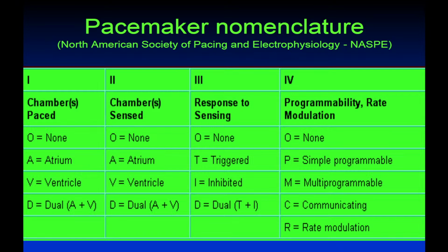We must take into account the pacemaker nomenclature by the North American Society of Pacing and Electrophysiology, NASPE. These devices have a few letters: the first letter means chamber paced, the second chamber sensed, the third response to sensing, and the fourth programmability and rate modulation. Sometimes we add a fifth letter, but this is the simplified nomenclature. We can pace atrium, ventricle, or both, dual. Chamber sensed may be atrium, ventricle, dual. Response to sensing: none, trigger, inhibition, or dual. And programmability and rate modulation: simple, programmable, multi-programmable, communicating, R.